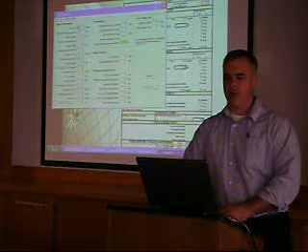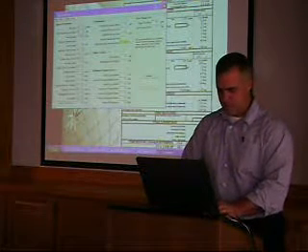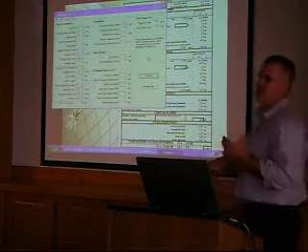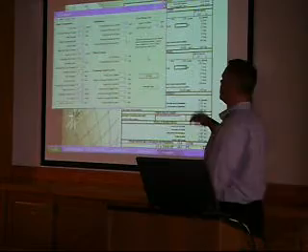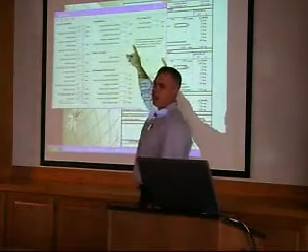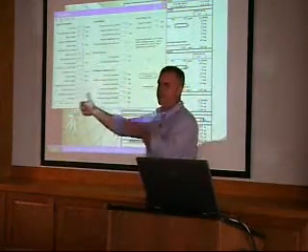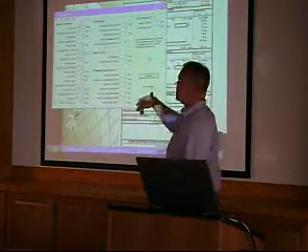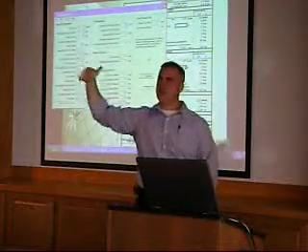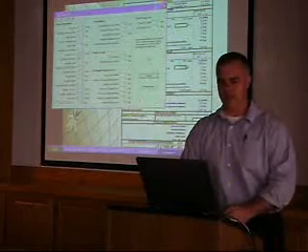Let's go to 3/16-inch holes. This is where we usually come into the ideal, the middle of the road. 3/16 hole sizes are kind of nice. We got 0.82 gallons per minute per orifice. We've got 17.3 gallons per minute per half, so 34 gallons a minute on the total system. And our flow differential is only 4.5 feet. So that's why sometimes that's a nice middle-of-the-road approach. We're going to pick 3/16-inch holes here.